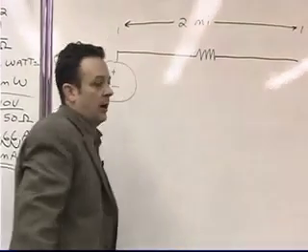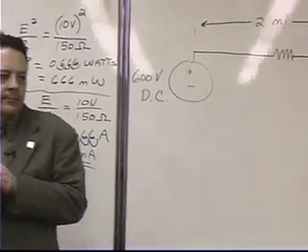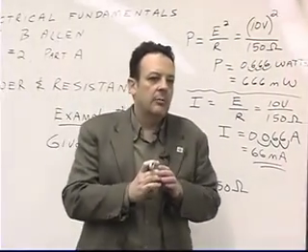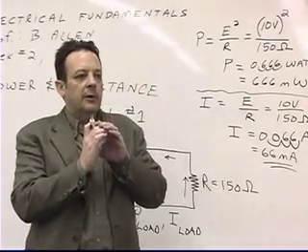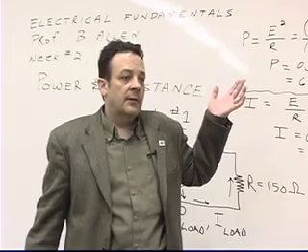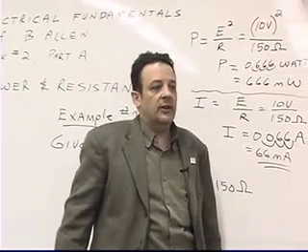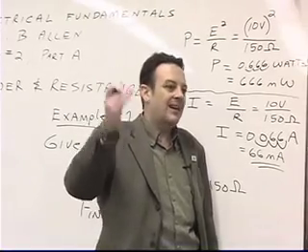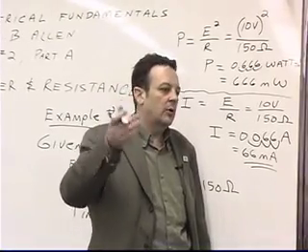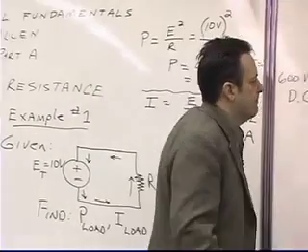And if we got 2 miles of cable, even if it's fairly large cable, say it's double aught cable or single aught cable, it's pretty big around, okay? It's going to have some resistance. And the manufacturer of the cable is going to usually designate the resistance in ohms per 10 feet, or ohms per 100 feet, or ohms per so many feet, okay?